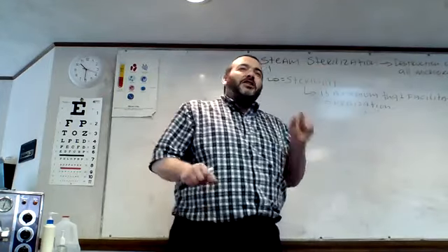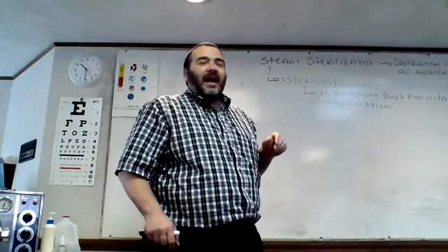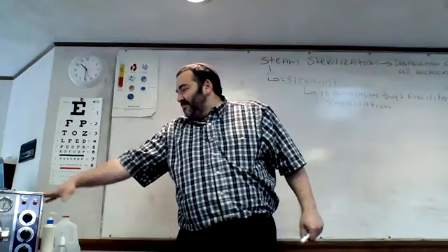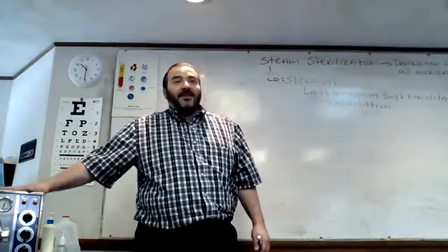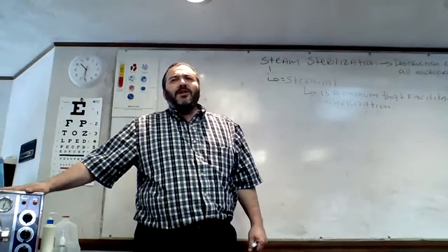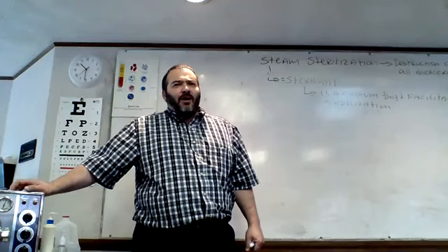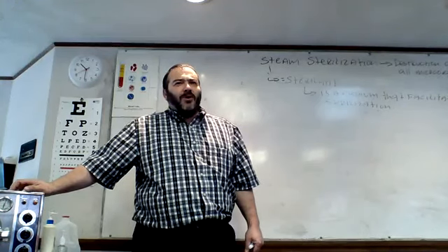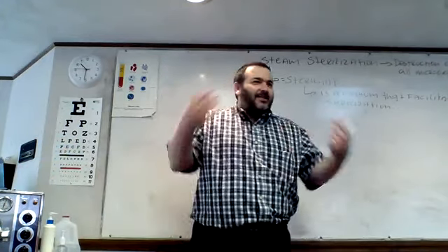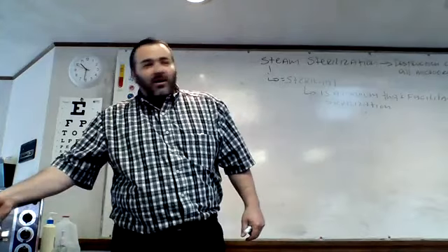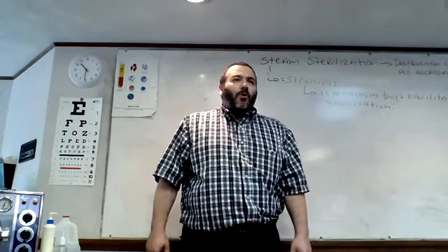Now imagine you're just a teeny little bug sitting on the end of your surgical instrument, and you are inside this machine right over here that we call the autoclave, or a steam sterilizer. And we keep building and building the pressure inside by boiling the water. It keeps turning into more and more steam, and the steam is getting collected inside that steel chamber with a solid door. Nothing is getting out, only staying in, so there's more and more pressure.